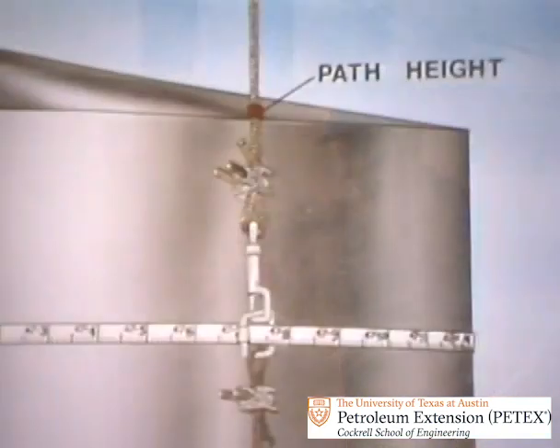Then, a path mark is made at the proper height, but it's not practical to mark the tape path all around the ring. It's too high. So the upper line is marked to indicate the height of the tape path. Then, one crewman on the tank roof holds the upper line with its mark at the top of the tank ring. This suspends the tape at the proper path height. Another crewman on the ground pulls on the lower line to keep tension on the upper line. A third crewman pulls in tape slack through the ring.